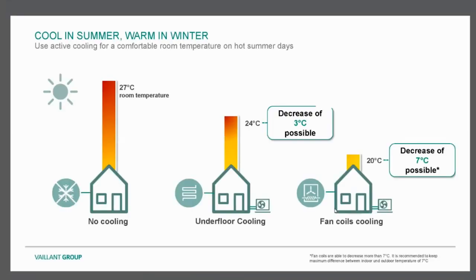One of the other things the system can do is cooling. Here's an example house, 27 degrees with no cooling. You can put underfloor or radiant cooling in, and you can drop that back maybe by about 3 degrees. But if you want really good high comfort cooling, you would use fan coils, which is a bit like air conditioning, which can be connected to the system, and then you can drop the temperature quite dramatically. And this sort of drop in temperature is more than adequate for most New Zealand applications.